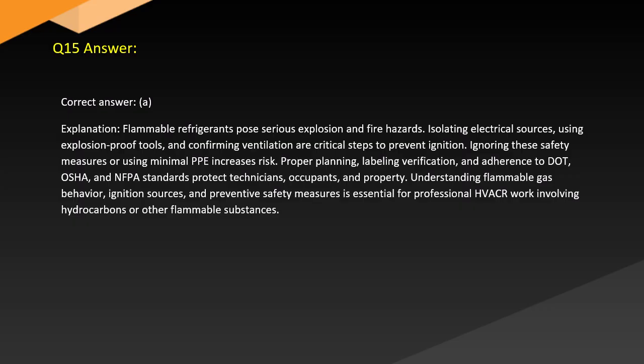Answer. Correct answer: A. Explanation. Flammable refrigerants pose serious explosion and fire hazards. Isolating electrical sources, using explosion-proof tools, and confirming ventilation are critical steps to prevent ignition. Ignoring these safety measures or using minimal PPE increases risk. Proper planning, labeling verification, and adherence to OSHA and NFPA standards protect technicians, occupants, and property. Understanding flammable gas behavior, ignition sources, and preventive safety measures is essential for professional HVACR work involving hydrocarbons or other flammable substances.